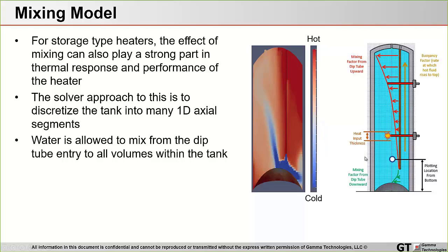And so GT Suite handles this by, again, discretizing this tank into many axial segments, and then having a certain amount of water that comes from the dip tube entry into multiple subvolumes throughout the tank. And so here you can see an example of the mixing model, where the mixing strength even grows as a function of distance towards the top of the tank. And so this is yet another phenomenon that's a very important consideration to model.